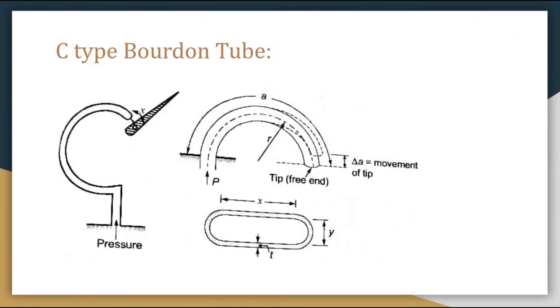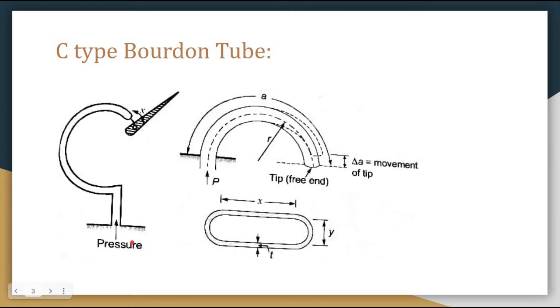The first category is the C-type Bourdon tube. As you can see in this diagram, one end called the tip of the tube is sealed and is called the free end. The other end of the tube is fixed to a socket where the pressure to be measured is applied. So the first end is sealed and called the free end, and the other end is fixed to the socket.